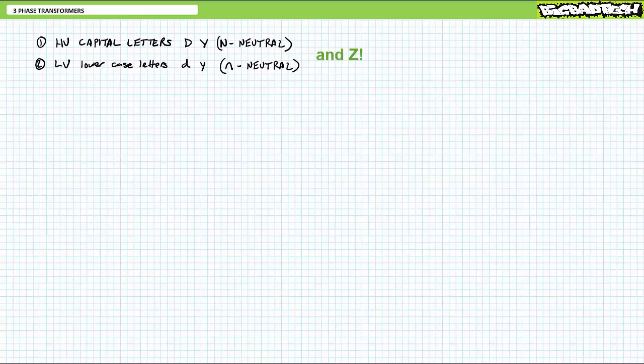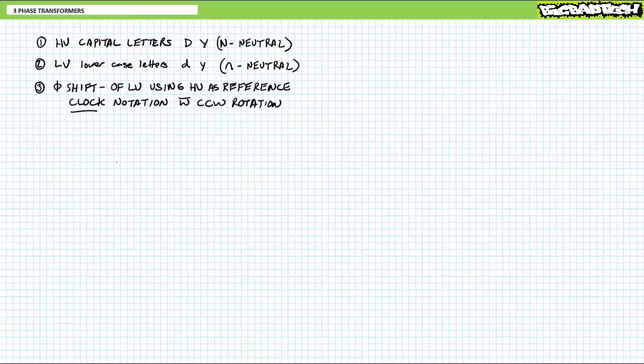Finally, part three is the phase shift of the low-voltage side with respect to the high-voltage side using clock notation. The high-voltage side is the reference — does the low-voltage lead or lag the high-voltage? This has important ramifications we'll explore in later example applications.